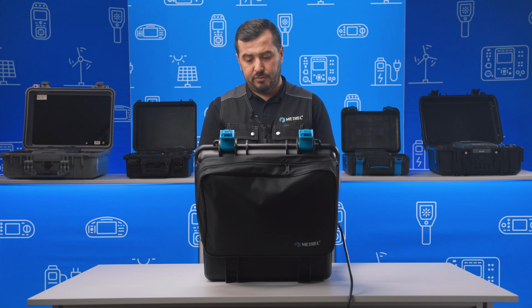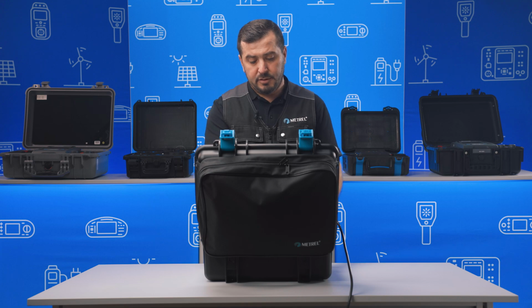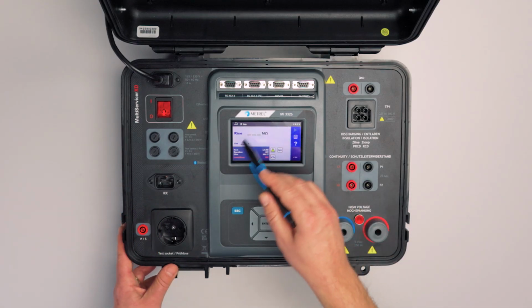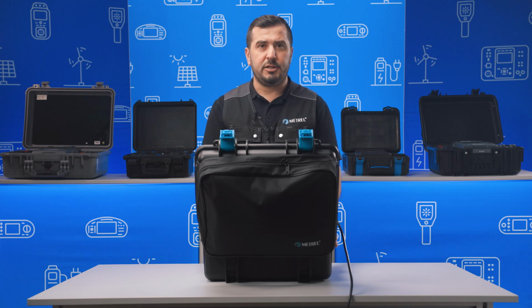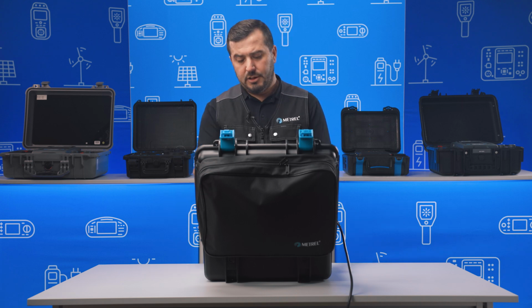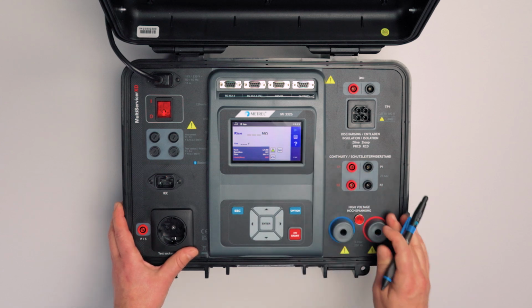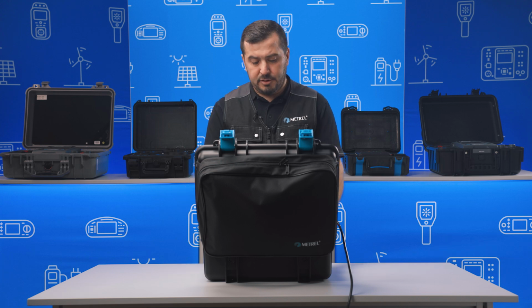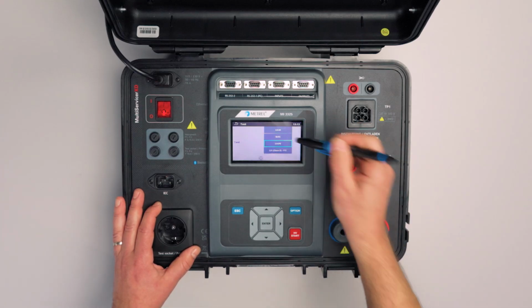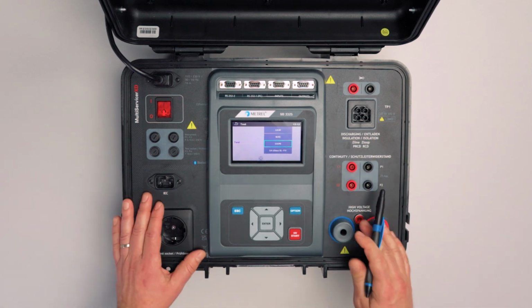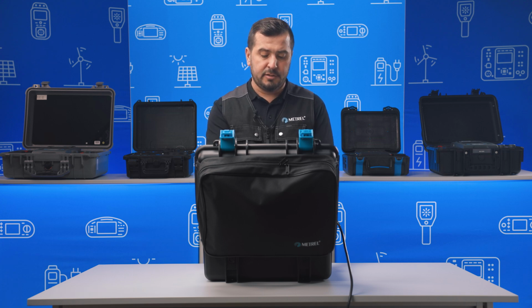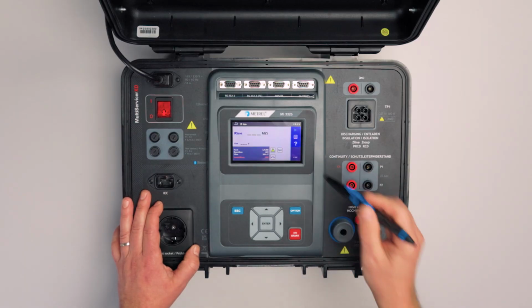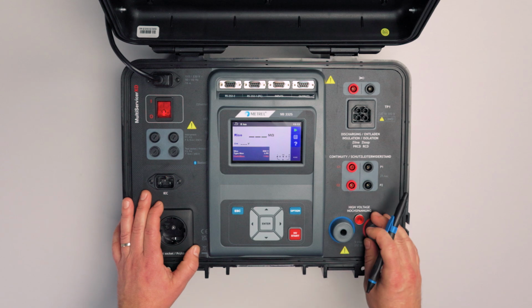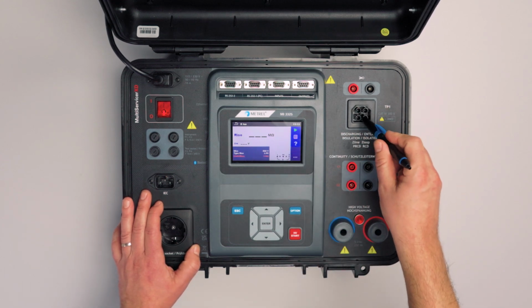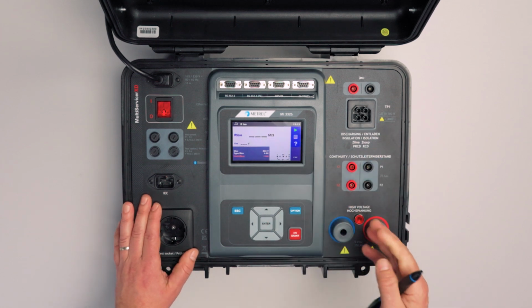The next in this group of insulation resistance testing is the one dedicated to testing insulation resistance on welding equipment. This group is supported only when using the instrument alongside the active three-phase adapter A1422. That's why it is also currently disabled here. We cannot start it. What is special about this measuring function is that we have different parameters depending on where on the welding equipment the measurement is performed. We can add the correct or appropriate parameter. Then we have the insulation resistance test, which is executed primarily via this multi-purpose test terminal. This one is dedicated to testing on switchboards or, let's say, part of electrical installation safety.